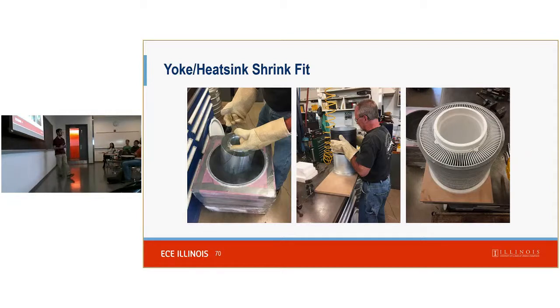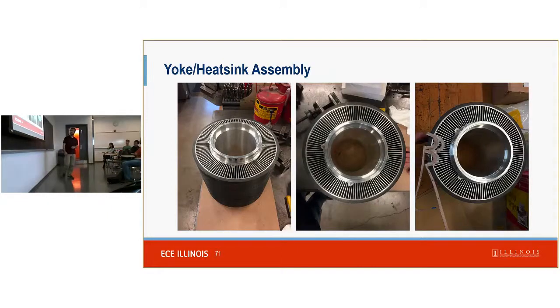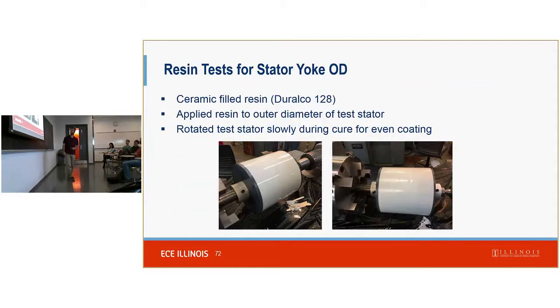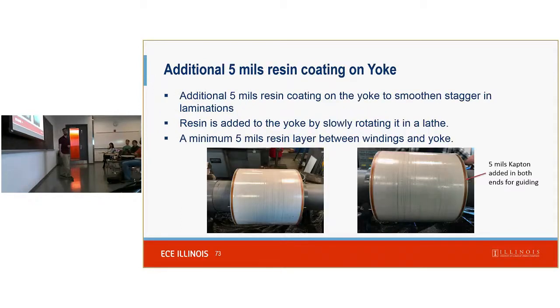And then once they neutralized to be the same temperature as each other, they fit very well together and will never come apart. So here's showing once they're assembled, and we can see the windings are going to attach there. But in order to mitigate the fact that on the outside as well, it was not a consistent or smooth surface, the ceramic-filled resin was applied to the outside. This is important also for the electrical insulation properties.